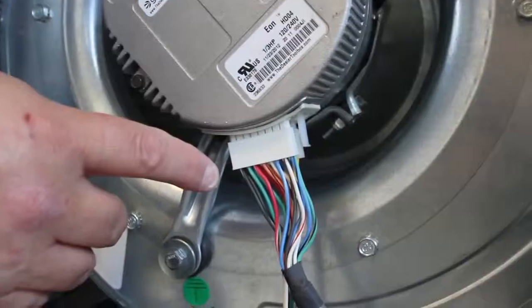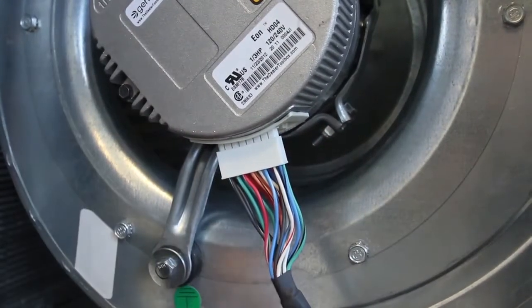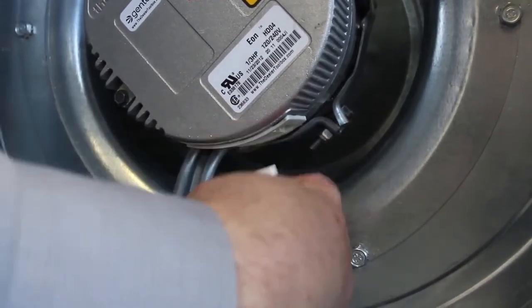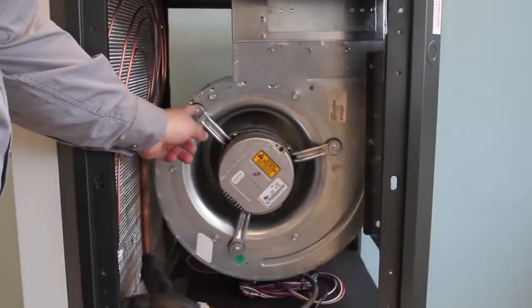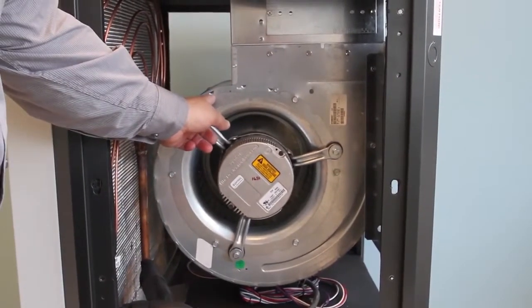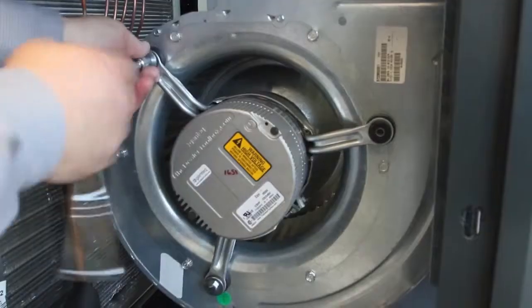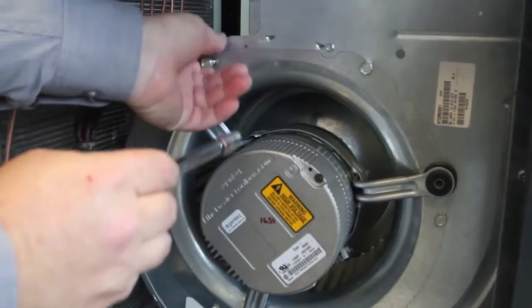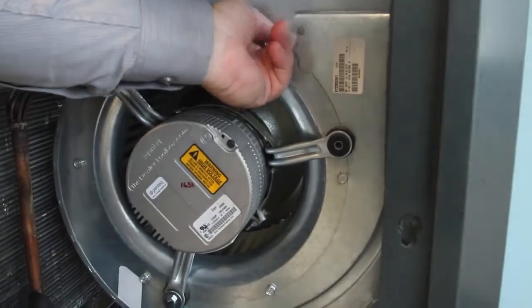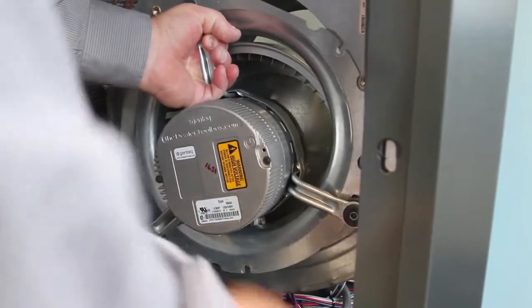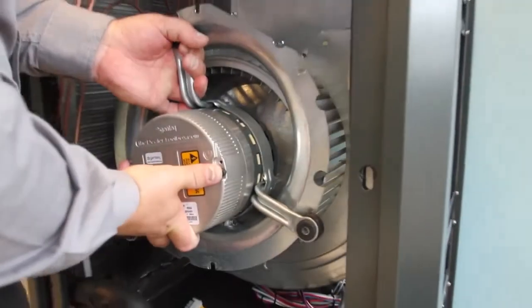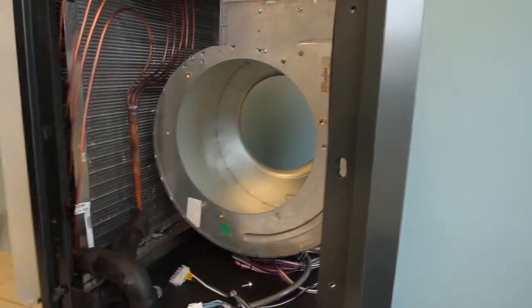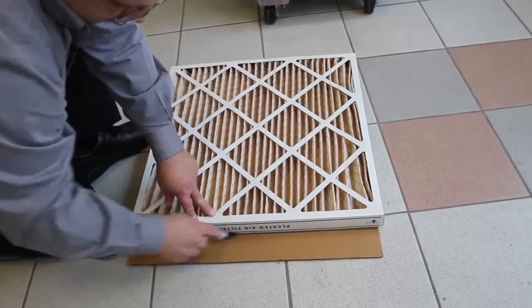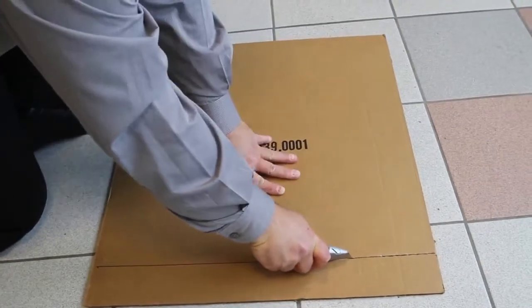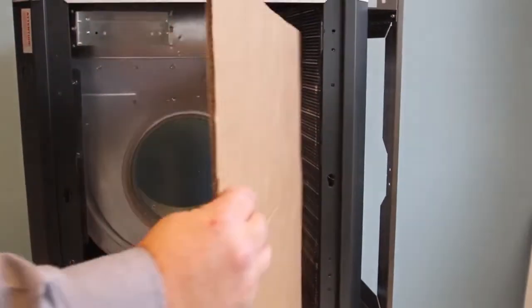Next, unplug the electrical connections of the blower motor and the ground wire connected to the blower housing. Then remove and retain the blower motor and inlet ring assembly by removing 3 bolts that secure the blower motor bracket and screws securing the blower inlet ring. And then carefully remove the blower and motor assembly. Once this is done, take a scrap piece of cardboard from the unit packaging and place between the blower and the air coil so that it cannot be damaged during the blower conversion.